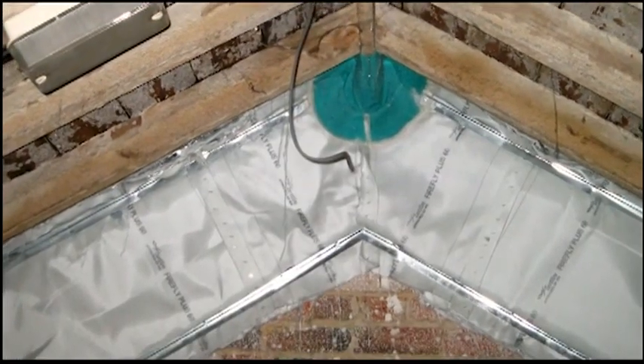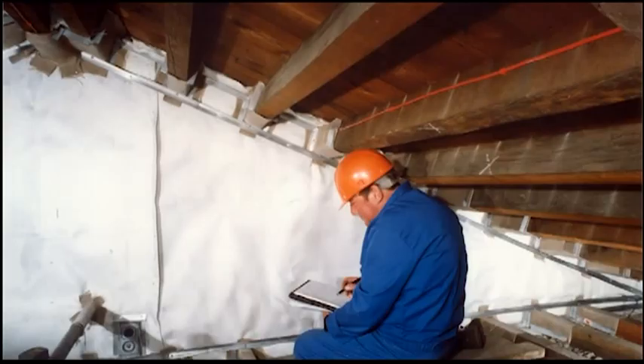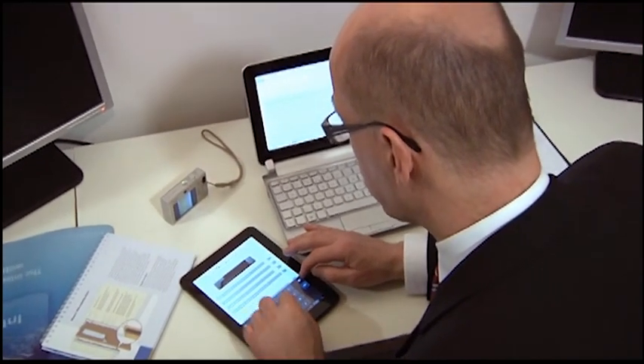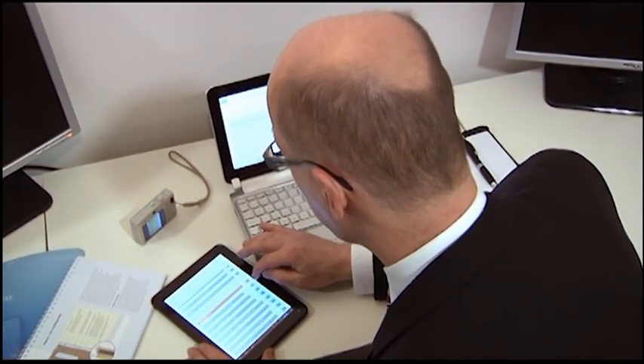Where visible, however, a fire risk assessor must ensure that cavity barriers are in place and not damaged. Any obvious or significant defects should be noted in the assessment and a full invasive third-party inspection should be considered.